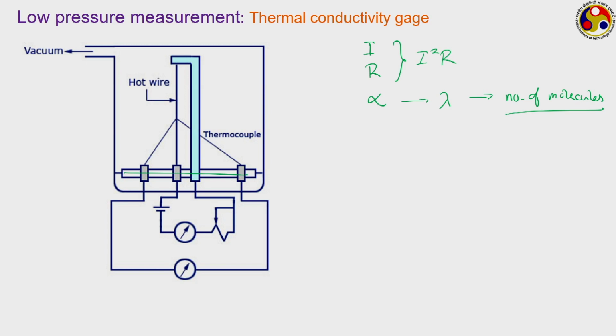One issue is that we have to keep the radiation small, so we use low emissivity materials, etc., so that conduction remains the primary mechanism. We can measure extremely low pressure, from 10 to the minus 3 up to 1 torr, at this level.